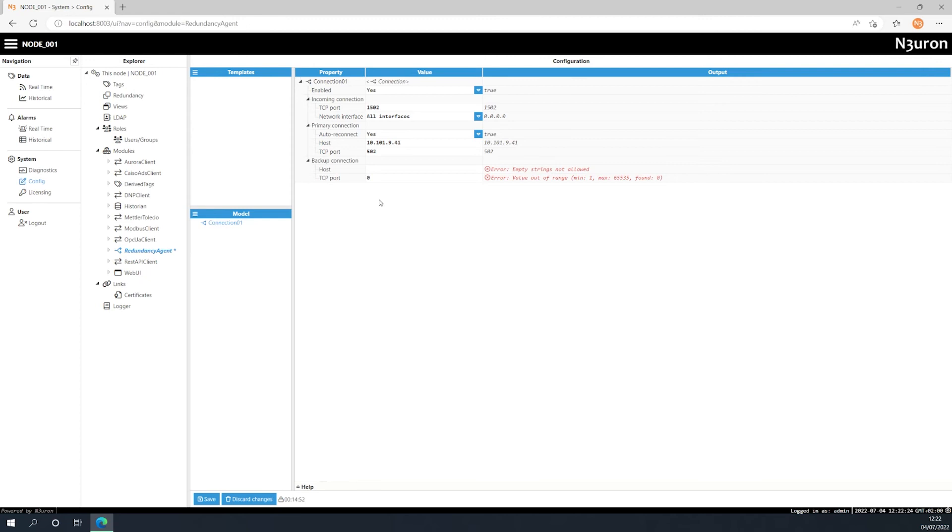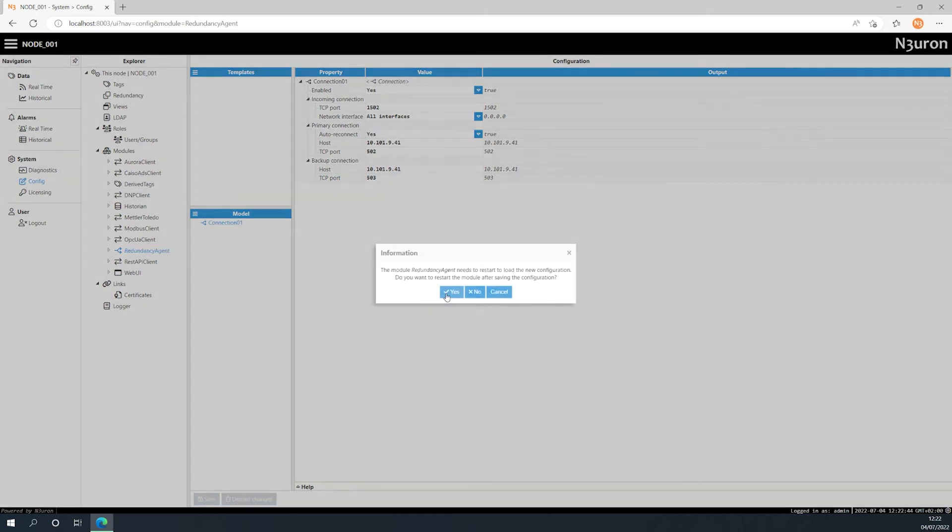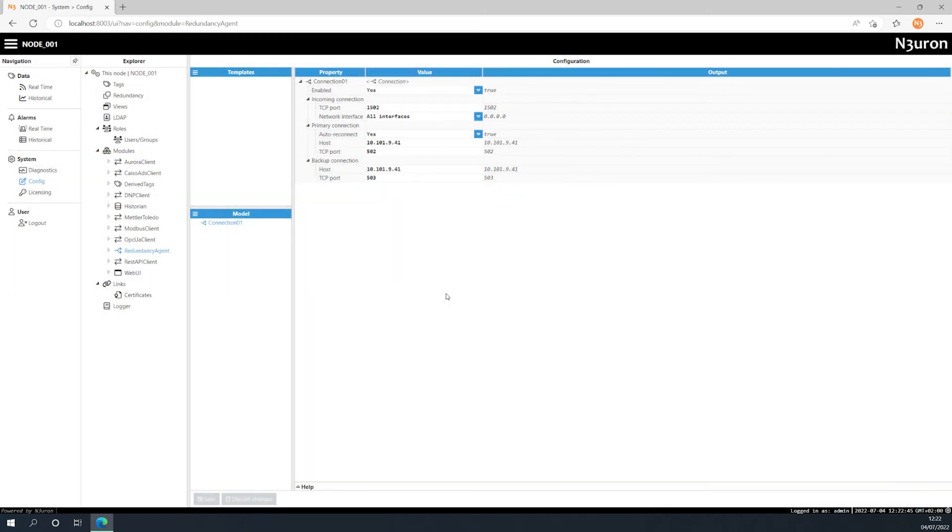When disabled, the agent keeps the connection to the backup server and switches back to the primary one only when the backup server fails. Now let's configure the backup connection. We will also use the same IP but this time the port will be 503. Once we save the configuration the redundancy agent starts.